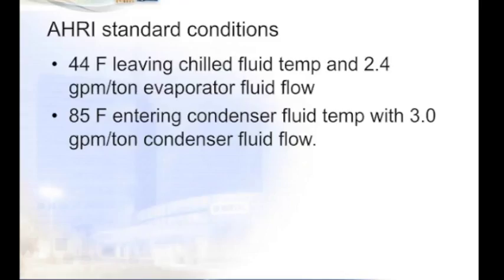Slide 15, yeah, the numbers increase from, as far as I know, those are the same standard conditions. The only difference between the earlier version was they added the GPM per ton evaporator fluid flow and a condenser flow as part of the standard conditions, which essentially results in a 10 degree delta T on the evaporator as well as on the condenser.